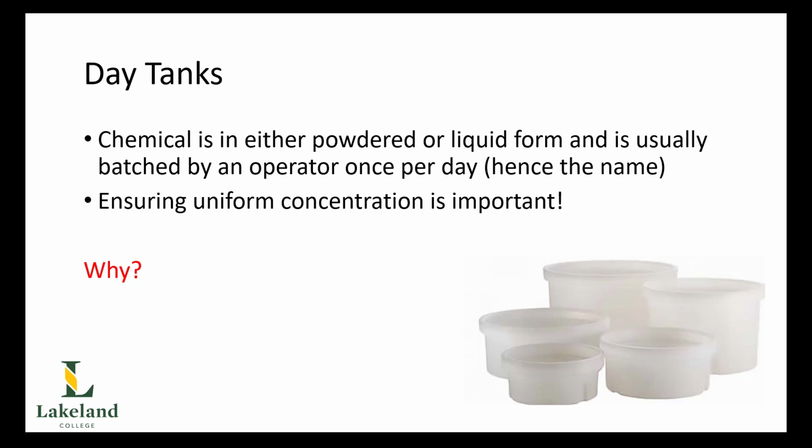Well, if it's slightly weak now on the mix because something went slightly off or it was mismeasured, then we'd need to increase the injection rates to offset the weak solution. Now the next person comes along and they batch it, and now it's too concentrated, it's too strong. Well, now we'd have to come back again and decrease the injection rate on the pump.